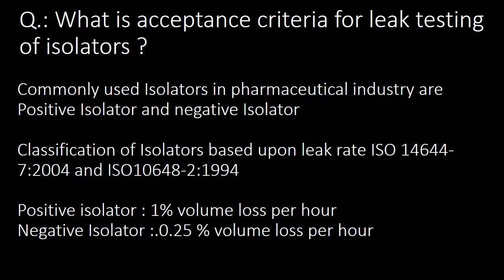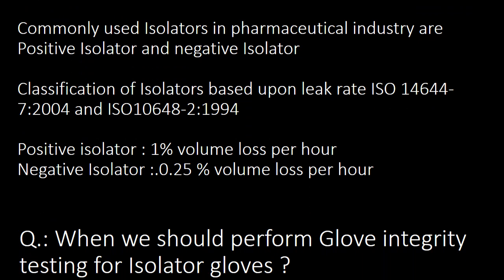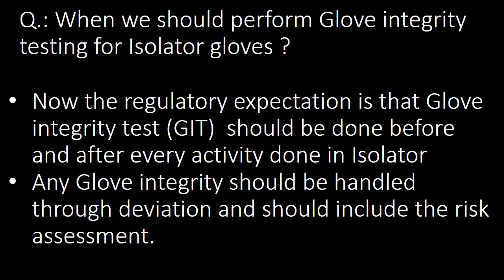The next important question: what is the acceptance criteria for leak testing of isolators? Commonly used isolators in the pharmaceutical industry are positive isolators and negative isolators. The acceptance criteria for positive isolators as per ISO is one percent volume loss per hour, whereas for negative isolators the acceptance criteria is 0.25 percent volume loss per hour.